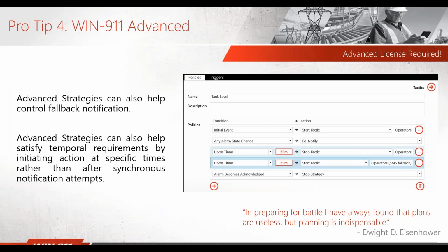Advanced strategies can also help control fallback notifications. So using the same or similar trigger upon a timer, you can say if you started an initial tactic or call out list as they start notifying operators, after 25 minutes, if the alarm hasn't been acknowledged, you want to start another tactic. Maybe the first tactic was all email and the second one is all SMS. You can assume that if an alarm hasn't been acknowledged in 25 minutes, maybe your notification attempts are failing. So 25 minutes later, start another tactic that goes out and uses a different notifier type.